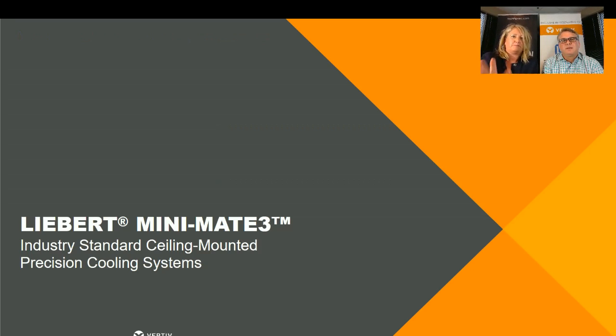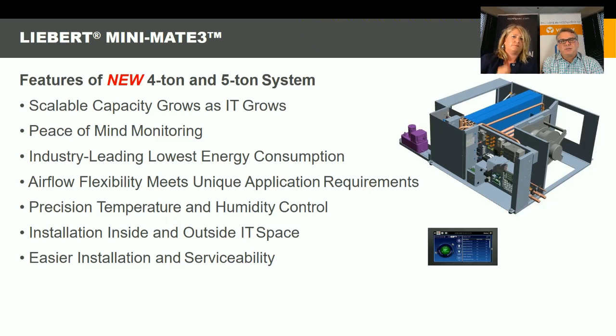That's correct. Okay. The next we're going to talk about is the new Minimate 3. This is a new product that came out this year. It comes in a 4 and a 5 ton size. The great thing about this is it comes with a digital scroll compressor and a variable speed EC fan. So to your point, if you start out with a low load in the space and over time you're going to build the heat load by adding racks or equipment, this unit will match that load both on the fan side and the compressor side. So it's a really good investment, is what you're saying. Exactly.